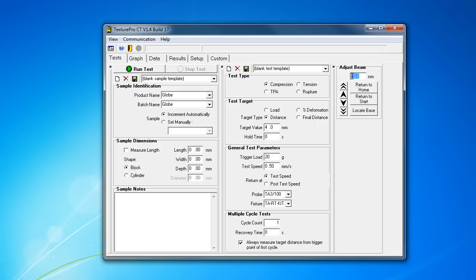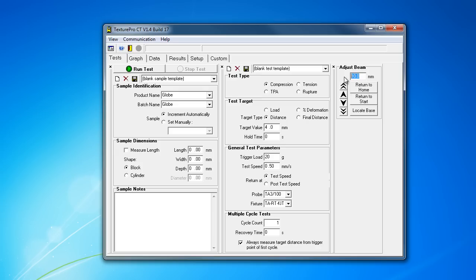You really only have two options for moving this probe. You've got up and down one millimeter or up and down ten millimeters. You end up playing this guessing game in terms of how close you want to be to the product, with the losing side being, you know, you hit your product and you've got to do it over again. What you'd think is that you'd be able to type into this number. You really can't. That's just there for seeing it. I'm pretty sure the Brookfield Software writer is just teasing you there. But, remember to write down this number because in any case that you change units or restart the program, your test location is going to be lost. Doing tests between days, you're going to have to manually write down where the beam is, just so you remain accurate in your tests.